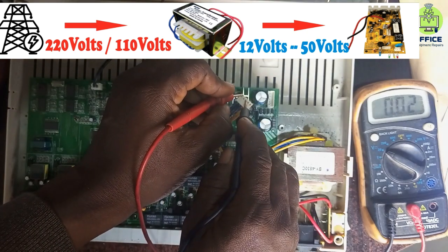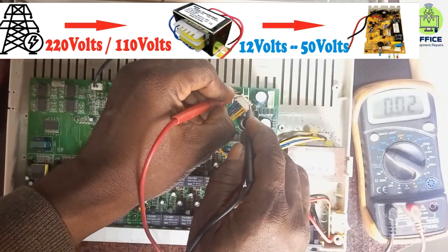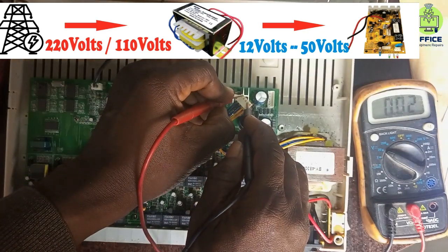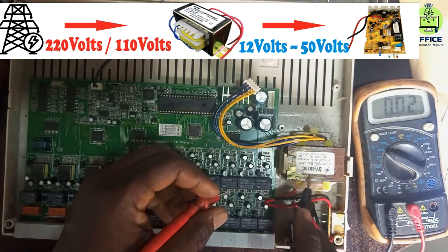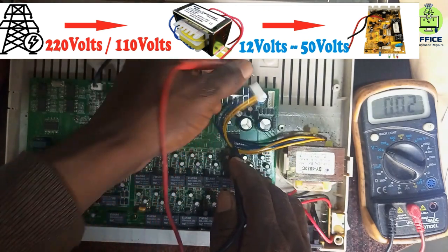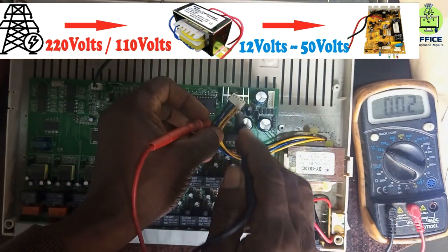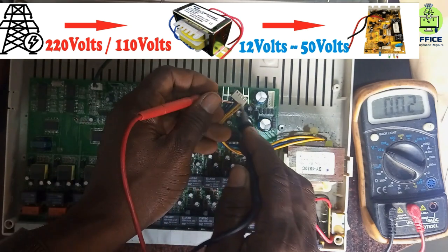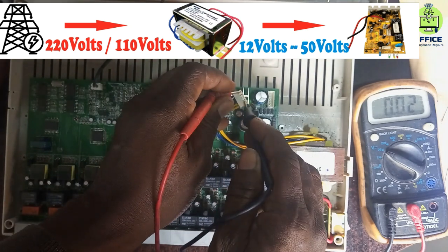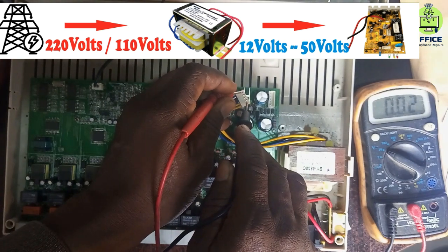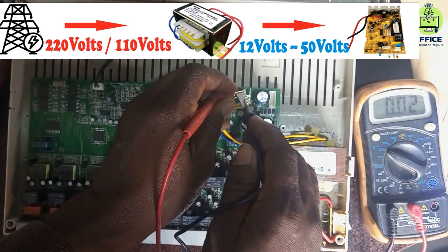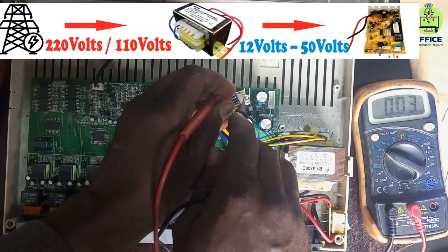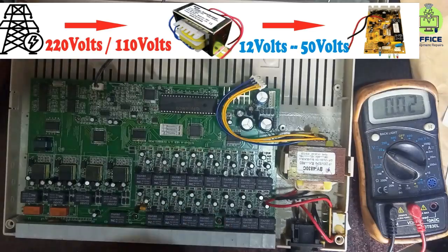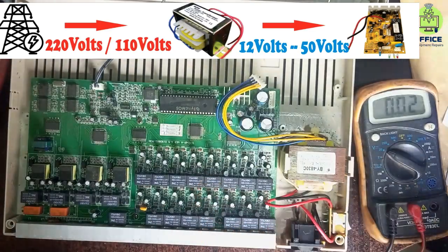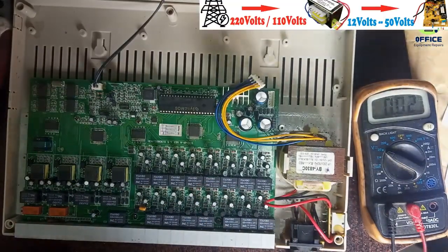So I'm going to check all of the contact points here, and there's no reading at all. No reading at all from this end. From the secondary end of this transformer, there is no reading at all. That means the transformer is not supplying any power to the board. And if it's not supplying any power to the board, it won't turn on or work at all. So most likely the problem is from this transformer right here.